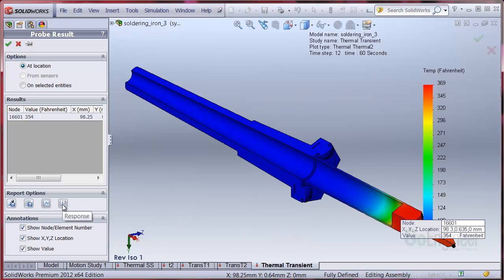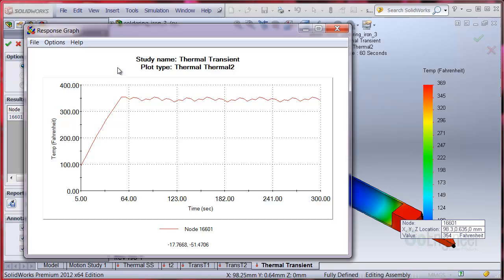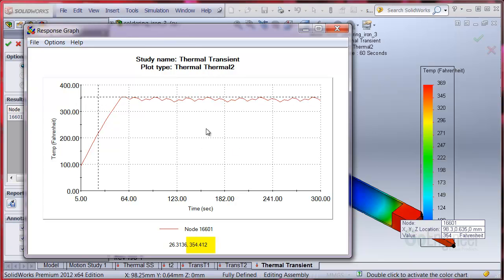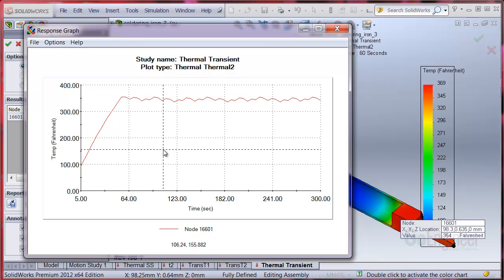Now let's choose the response option to see the tip temperature against time. On the graph, you can see the low temperature is about 336 and the high temperature is about 354. Recall we need to hold the tip temperature to about 360 F so it's not getting hot enough.